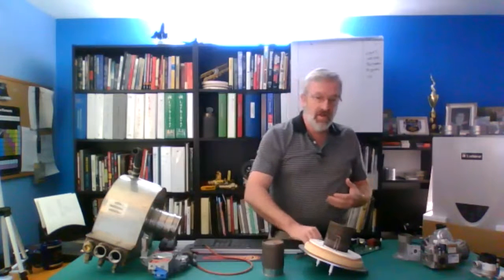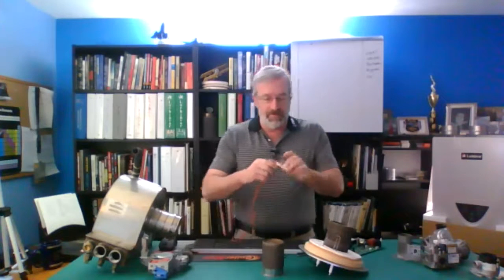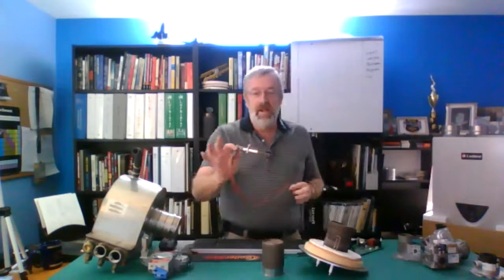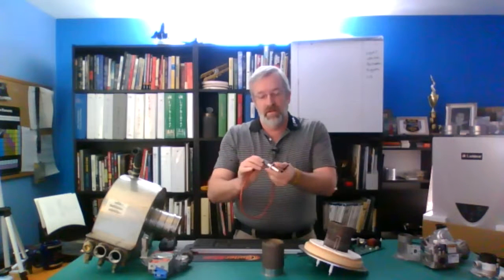So if I've walked through this, I've got 8 inches of gas, my gas valve opens, and I got a decent drop, let's move to the next thing in line. Next thing in line I like to check is the spark, okay? So I want to check on the spark. Here's your spark electrode, basically connected to the cable.